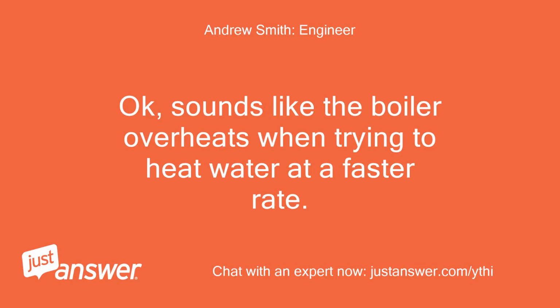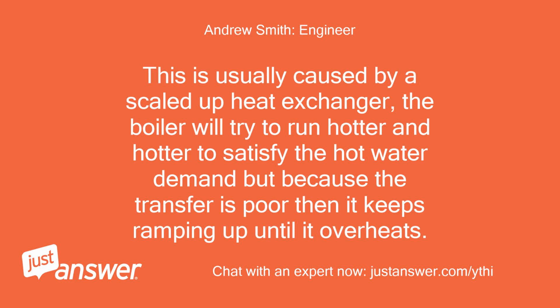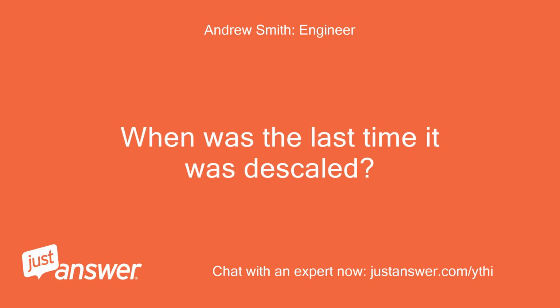Okay, sounds like the boiler overheats when trying to heat water at a faster rate. This is usually caused by a scaled-up heat exchanger. The boiler will try to run hotter and hotter to satisfy the hot water demand, but because the transfer is poor, it keeps ramping up until it overheats. When was the last time it was descaled?